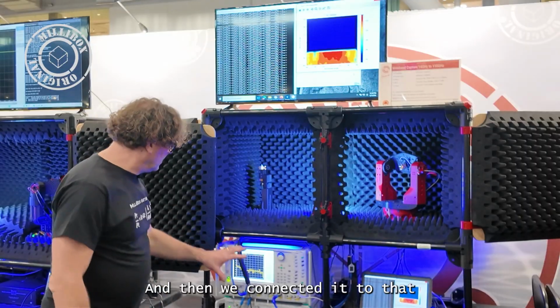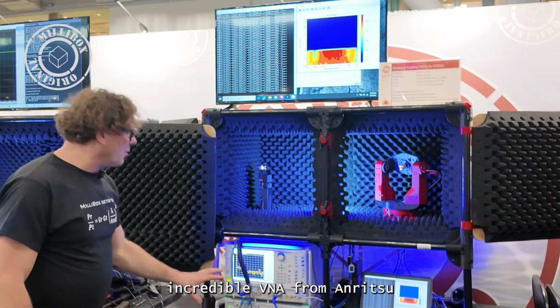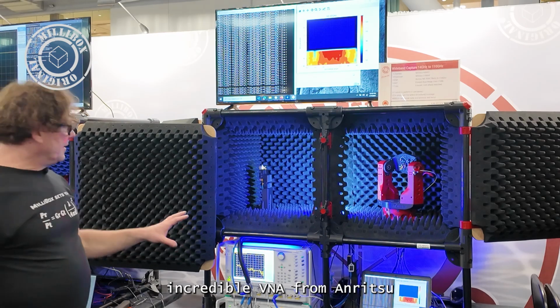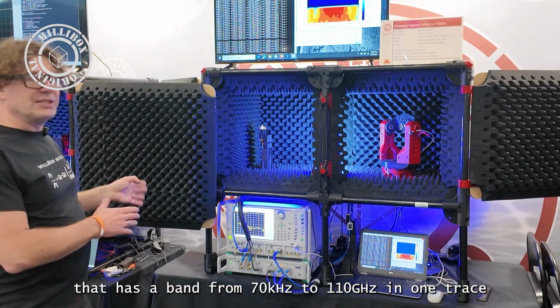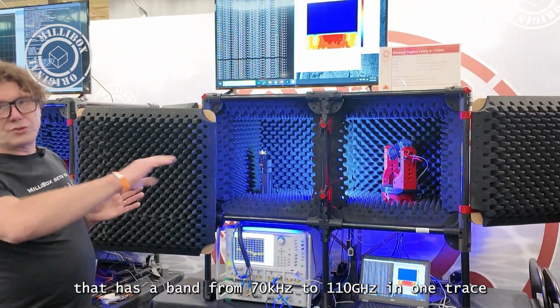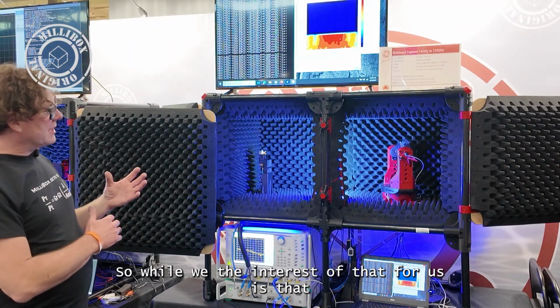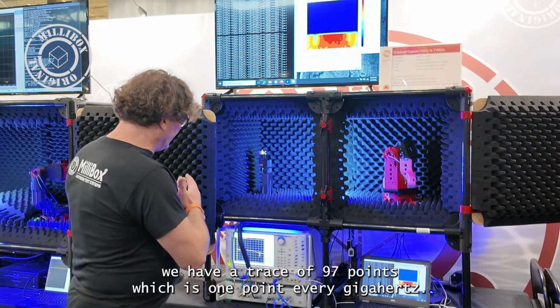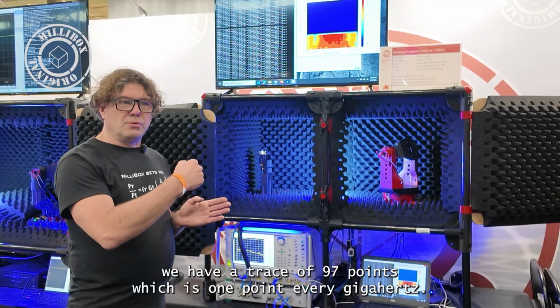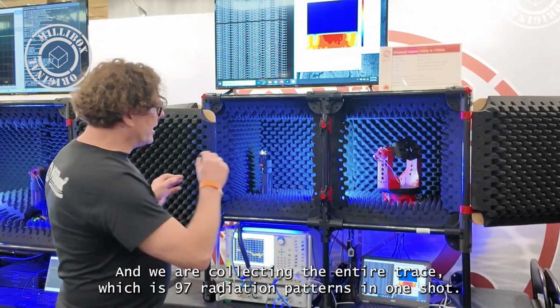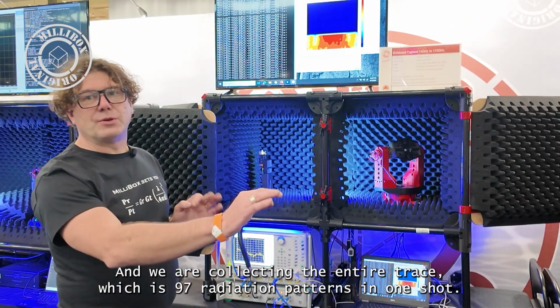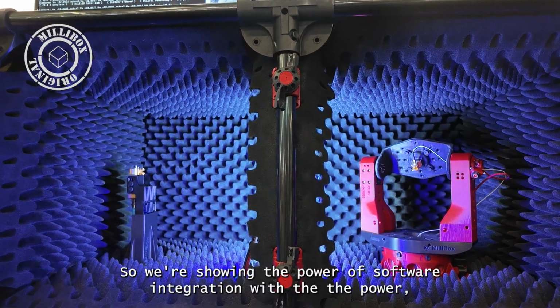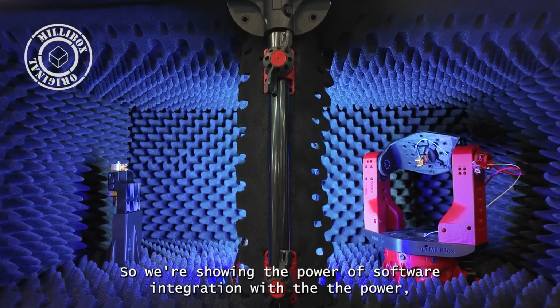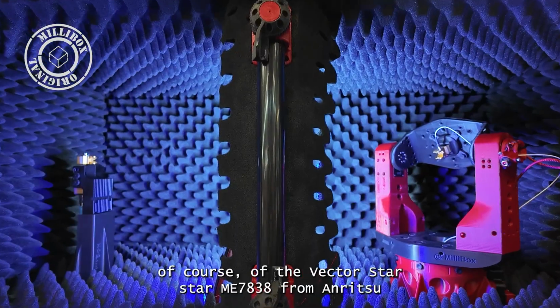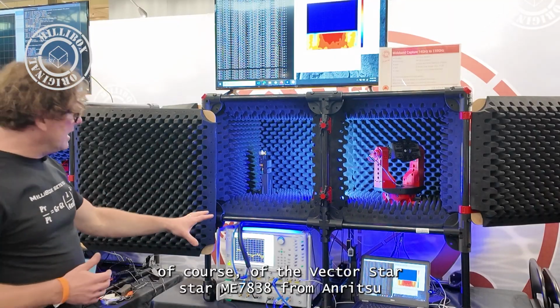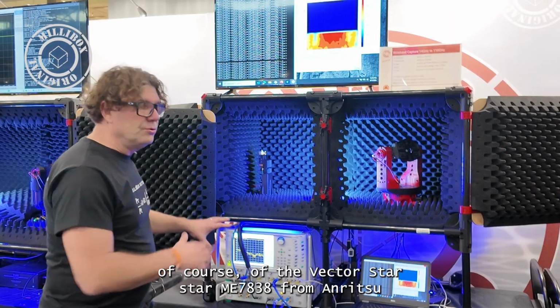Then we connected it to that incredible VNA from Anritsu that has a band from 70 kHz to 110 GHz, one trace. What's interesting for us is that we have a trace of 97 points, which is 1 point every gigahertz, and we're collecting the entire trace, which is 97 radiation patterns in one shot. So we're showing the power of our software integration with the power, of course, of the VectorStar ME7838 from Anritsu, and we combine.